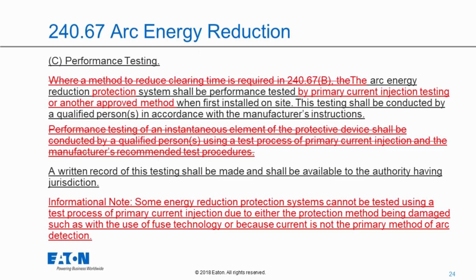The last thing I want to cover with regards to arc energy reduction requirements is in the 2020 code, we now make you, not only do we make you document where the location is, we make you document that either the fuse or the technology will operate in the parameters needed. But we also now, in the 2020 edition, make you do performance testing. And this is an entirely new section. Don't let the crossed out text confuse you. If you look in your NEC book that you purchase, you won't see that crossed out text.